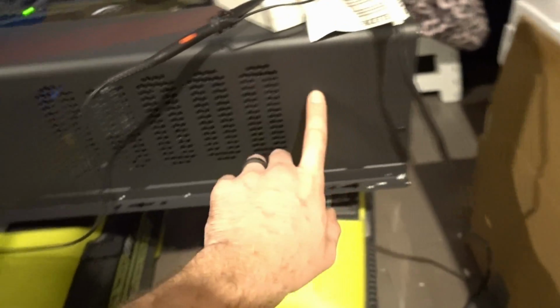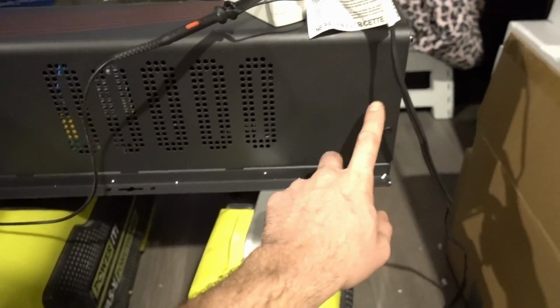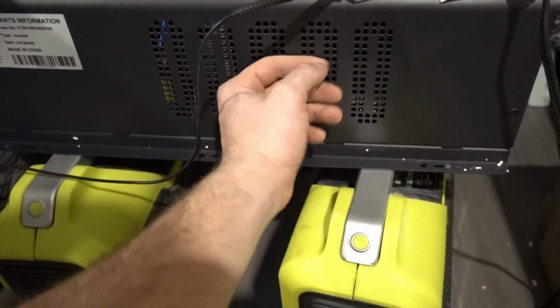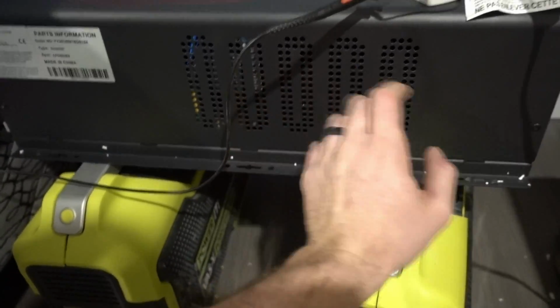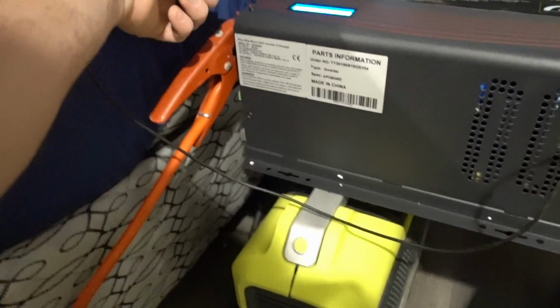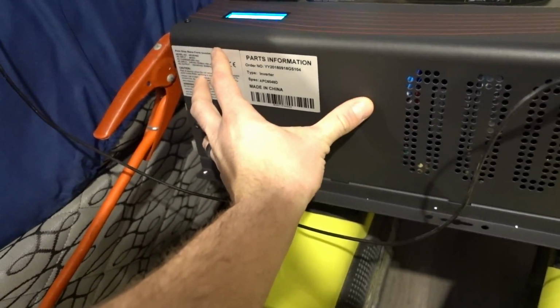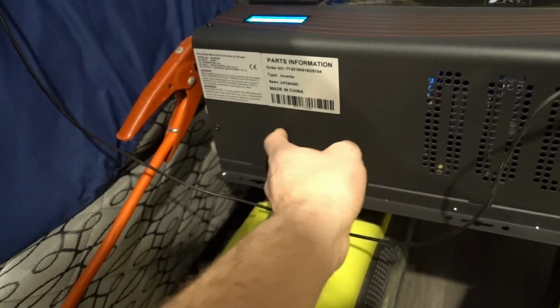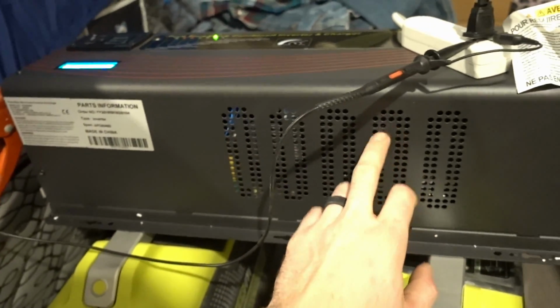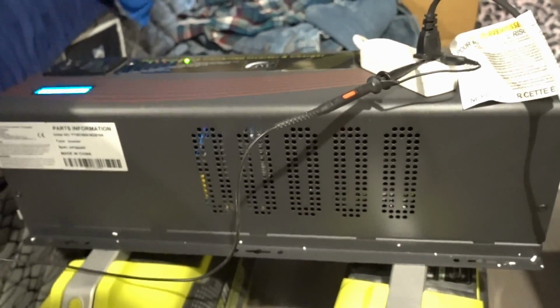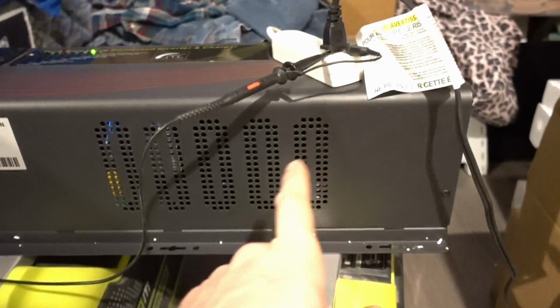Very interesting, so they have this one, this is where the transformer is. So they have the bigger fan pulling air and it's sucking in here, and that one pulls quite a bit more air than the smaller fan over here that's pushing in. And this one's just supplying the circuit board and the heat sinks enough air to stay cool. It looks like the transformer is what gets the hottest on this inverter from the design of their cooling.